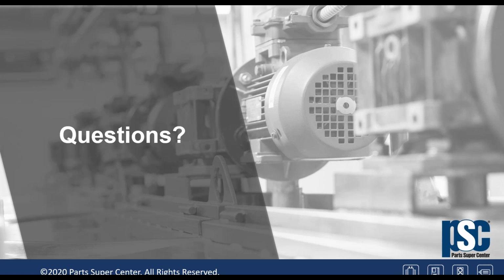And then we said, if I have this arcing occurring in a vacuum interrupter, now I won't be contaminating the oil. Now, what we call a vacuum bottle is in effect a vacuum interrupter, which means that's where the arcing occurs, in the vacuum. In theory, there shouldn't be any arcing in the vacuum because there's no oxygen to burn. When we talk about load tap changers, we have two kinds: the arcing type, which is the one we had before, and the vacuum type, the latest design that we came up with. So a vacuum bottle is nothing more than a vacuum interrupter.